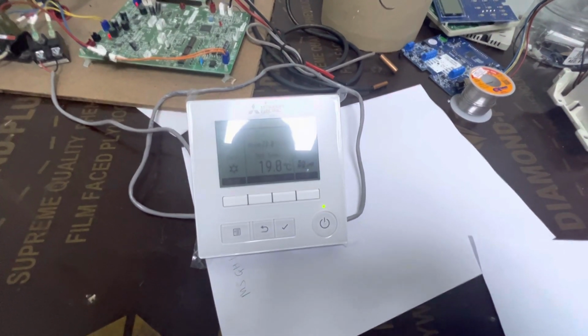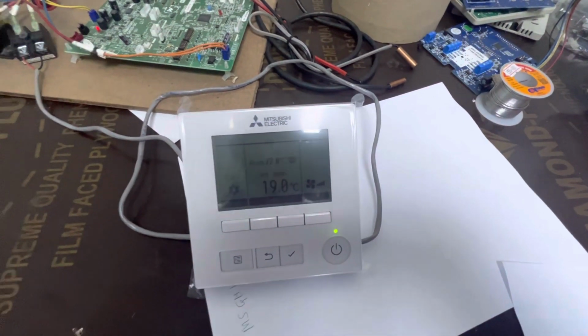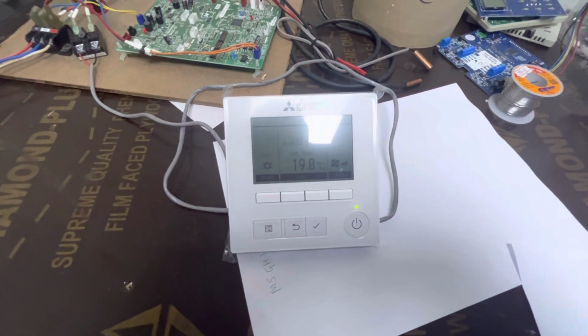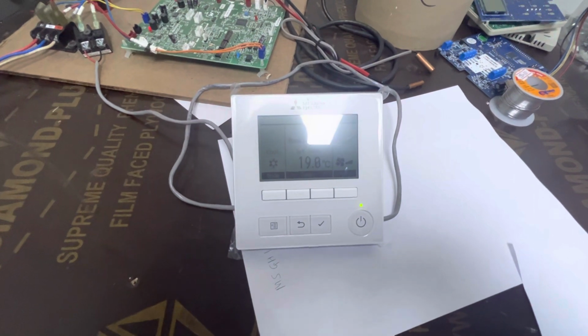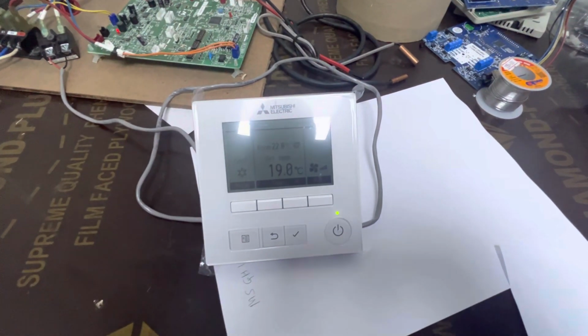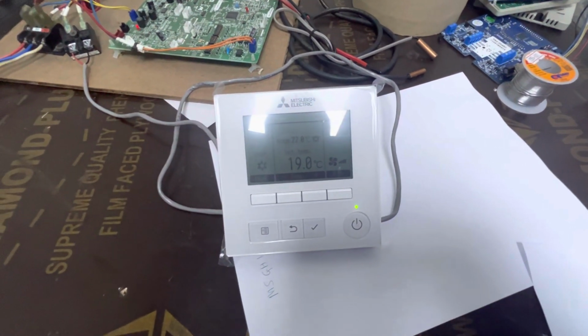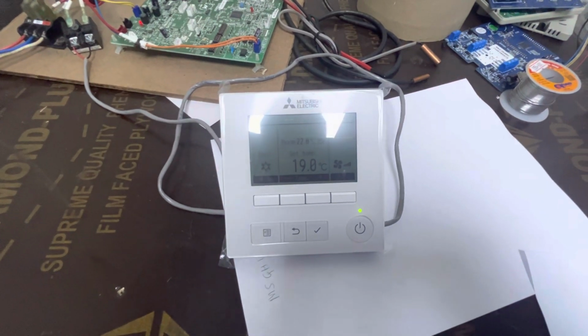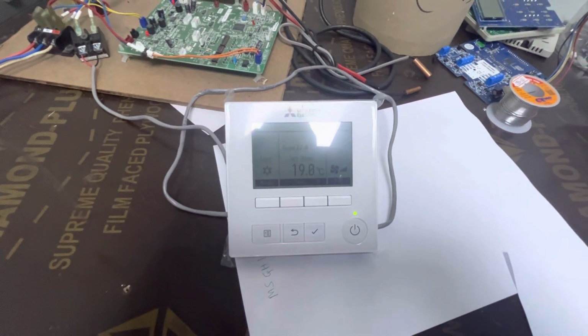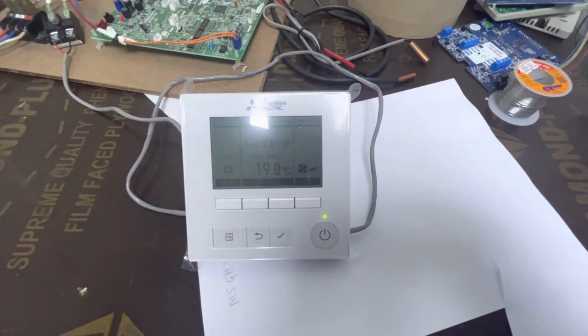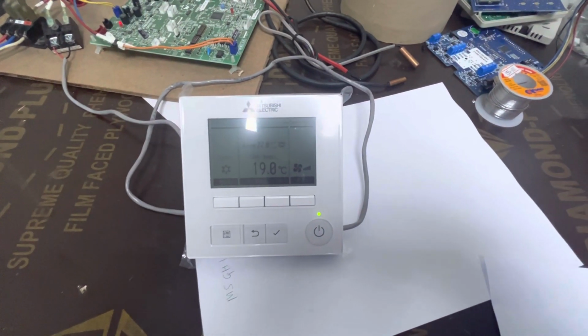Today we are going to explain how to change the static pressure setting for the ducted model. Because the ducted model depends on the ducting length and the number of elbows in the ducting, there will be a static pressure loss. To compensate for that loss, you need to adjust the static pressure setting during commissioning time.